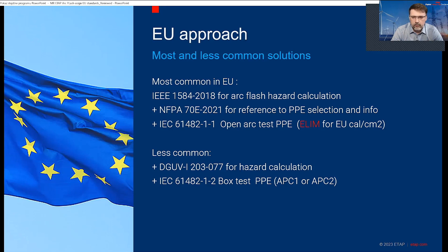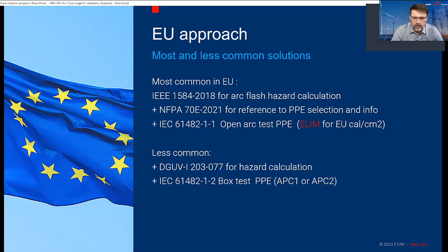The less common approach — which is what we're comparing today — is DGUV Information 203-077 for arc flash hazard calculations, combined with IEC 61482-1-2 for the box method test for PPE, which gives APC (arc protection class) 1 and APC class 2 — the only two classes available.